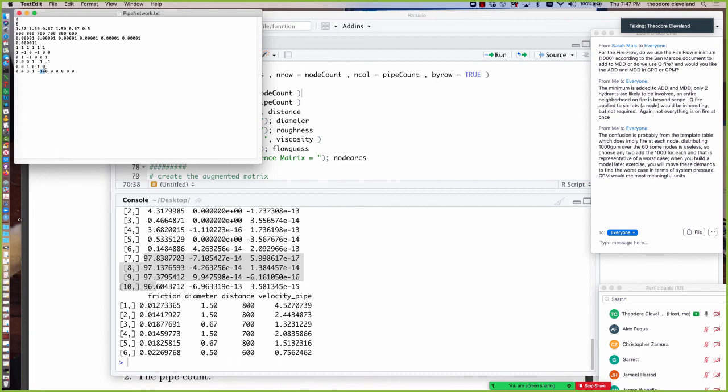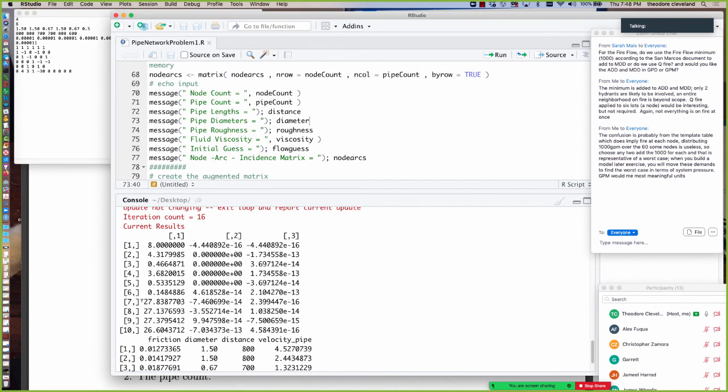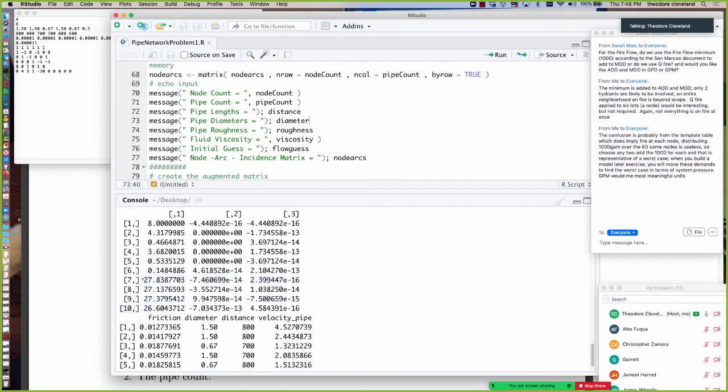Let's suppose the fixed grade node, instead of being at 100 feet, is instead 20 feet of head. So not very much. Well, actually, let's just go to 1 atmosphere. So we'll put 30 feet of head in the fixed grade node. Since we haven't specified node elevations, we can initially play the game that they're at elevation 0, and we'll see how much head is remaining in the system. Rerun the thing again and find out that actually that works pretty good because we increase the pipe diameters.